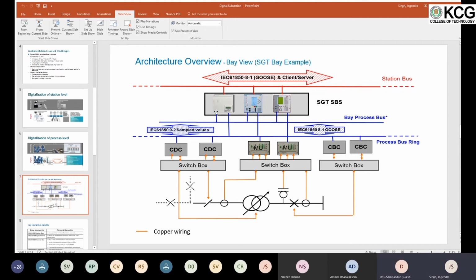And to change a device, let us say a CT, you need an outage. And why would you want to change it if it is serving your purpose? It is a costly thing. So unless the life is gone, or there is a fault, the circuit breaker or CT has gone bad, then you change it. At present in National Grid UK we are not planning to change to optical CT immediately, because National Grid has not installed any fully digital substation as of today.